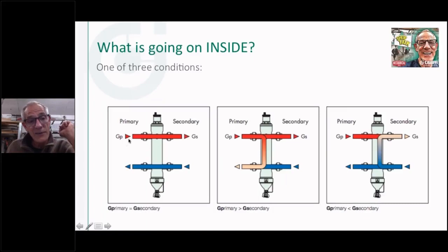So let's say I've got 40 gallons a minute here. I might have an application where I've only got a 30 gallon per minute load when I'm at design condition. Maybe I'm running a different delta T over here. You don't add the 40 gallon per minute that the boiler needs plus the 30 gallon per minute that the distribution needs and say, well, I need a 70 gallon a minute hydro separator. It's the larger of the two.